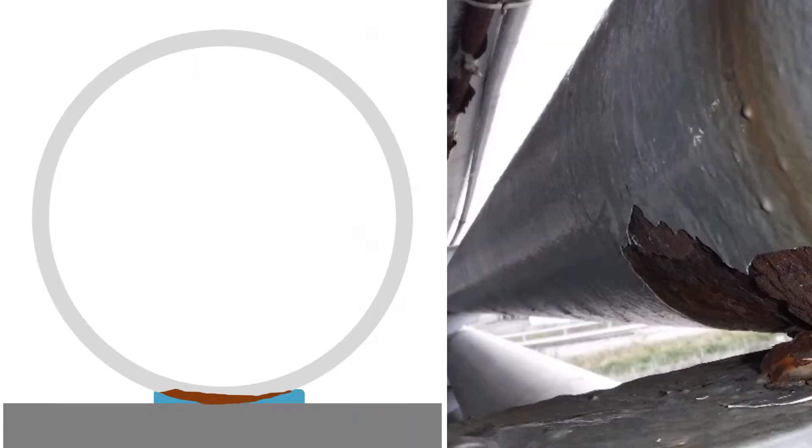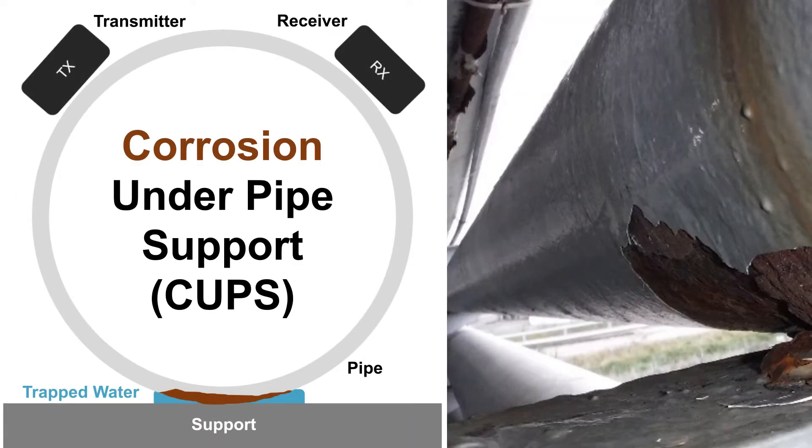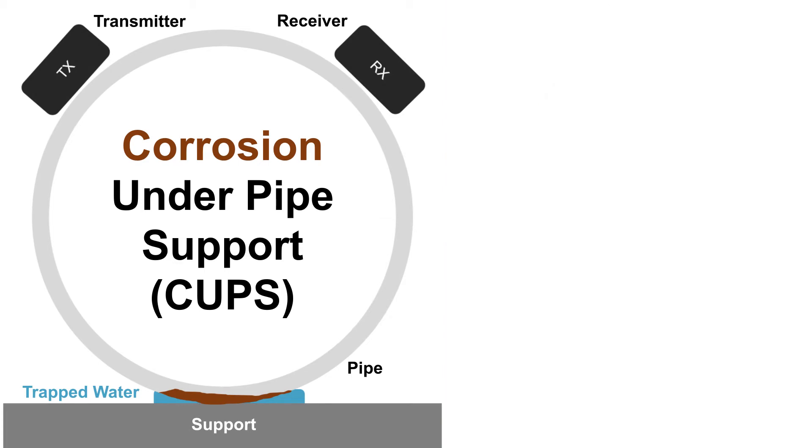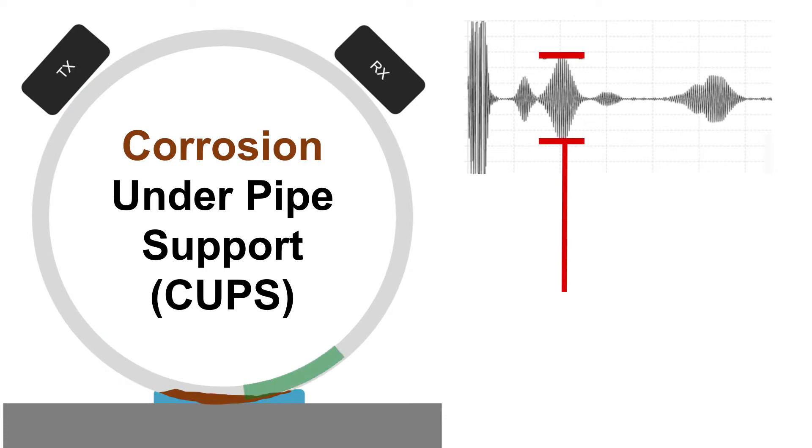Corrosion under pipe supports can be inspected using ultrasonic or guided wave scanners. Typically, the waves would interact with the defect and the reflected or through transmitted wave amplitude is used to estimate the defect severity.